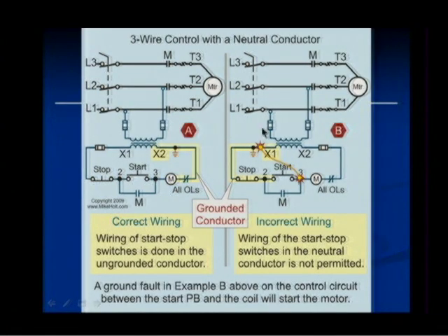Right. What happens a lot of times is if you have a starter bucket, sometimes it's called that, with everything included, then the field wiring is attached to a terminal strip or barrier strip that's in the manufactured product. And so you're only going to be connecting external wiring to the barrier strip in the equipment. All right, but let's just review this again. If you somehow use your neutral, because the neutral is going to be grounded here, as part of your control wiring, you could have a fault to the neutral to another conductor that could bypass the start button, and it could cause the motor to start and run, and you have no way to stop it, no way to control it.